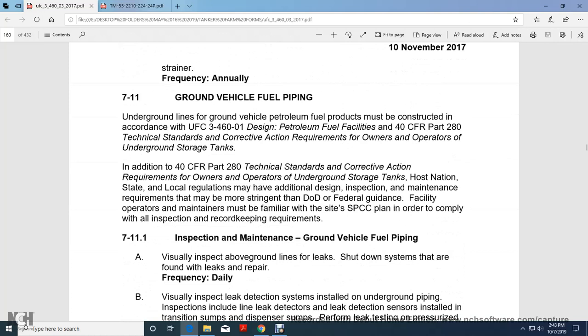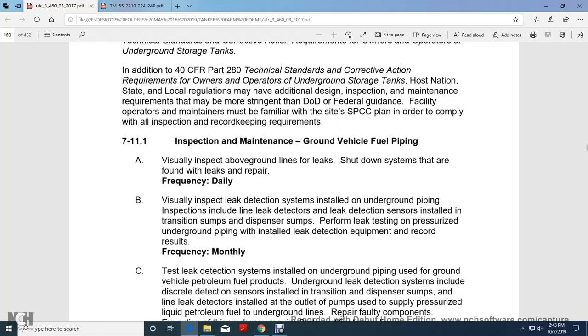7.11 Ground vehicle fuel piping. Underground lines for ground vehicle petroleum fuel products must be constructed in accordance with UFC 3-460-01 Design: Petroleum Fuel Facilities and Title 40 CFR Part 280, Technical Standards and Corrective Action Requirements for Owners and Operators of Underground Storage Tanks. In addition to Title 40 CFR Part 280, host nation, state, and local regulations may have additional design, inspection and maintenance requirements and may be more stringent than DoD or Federal guidance. Facility operators and maintainers must be familiar with the Spill Prevention Countermeasure plan in order to comply with all the inspection record keeping.